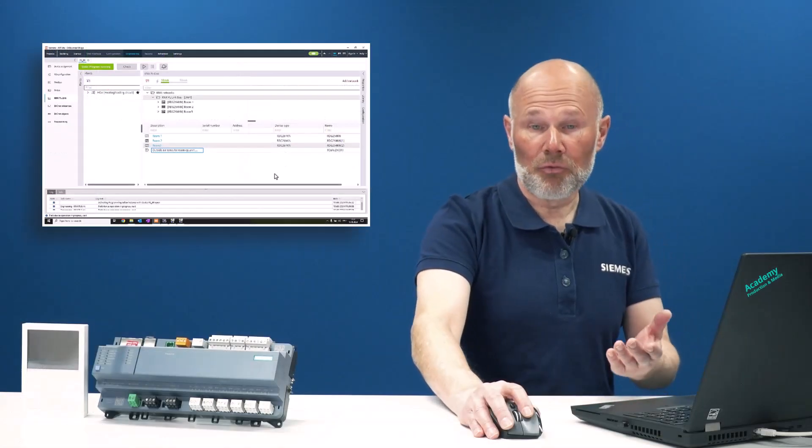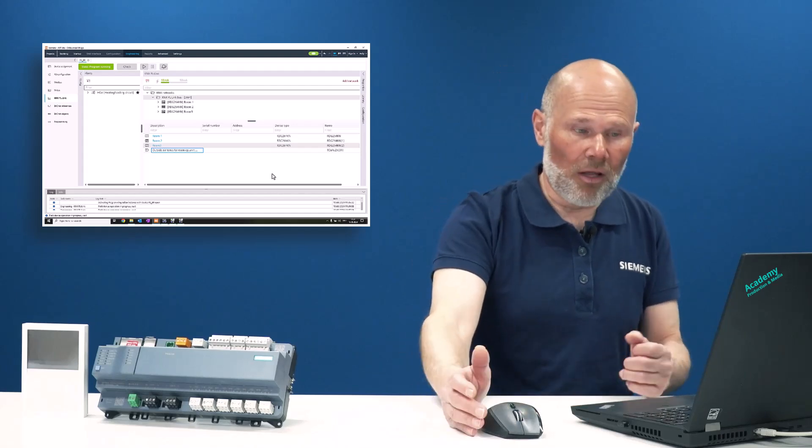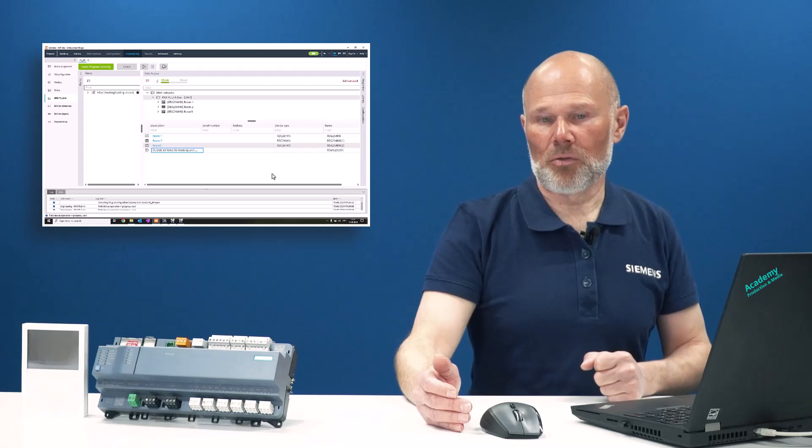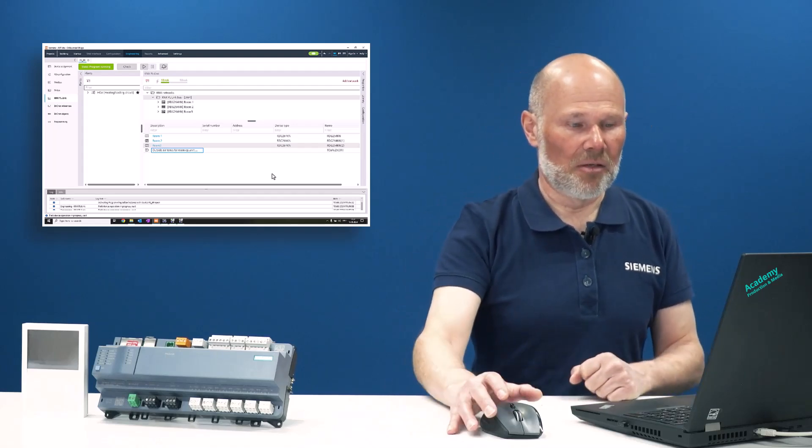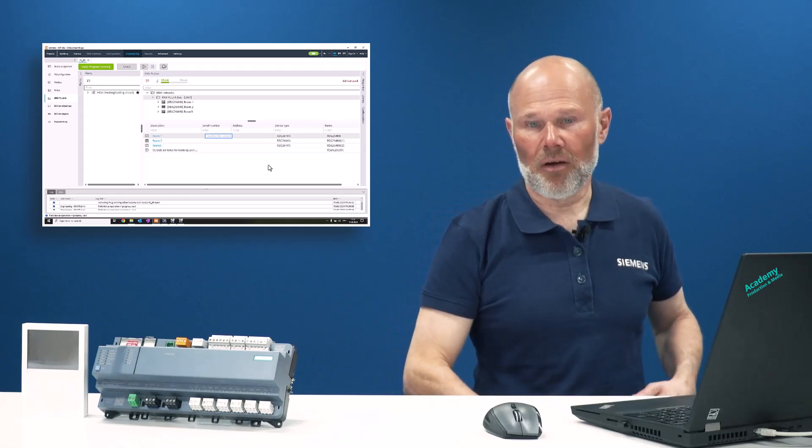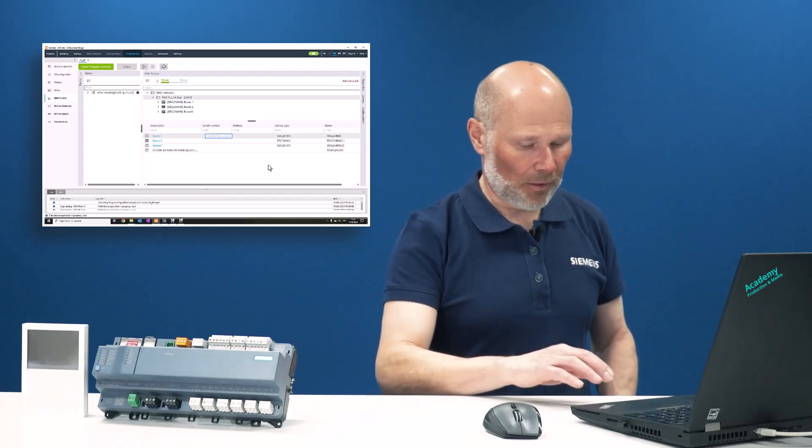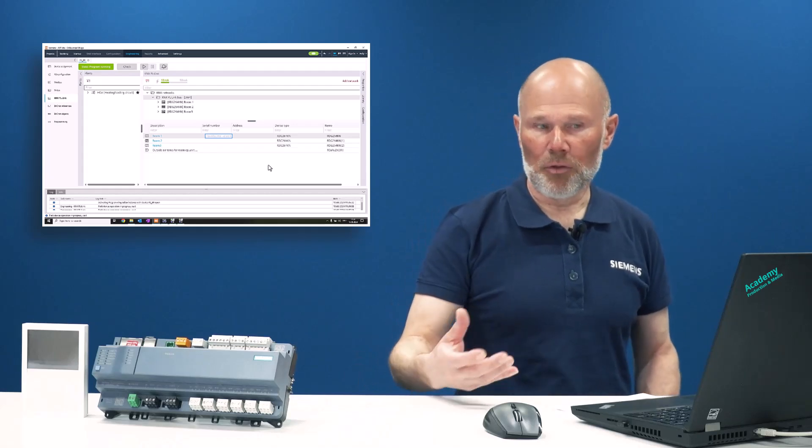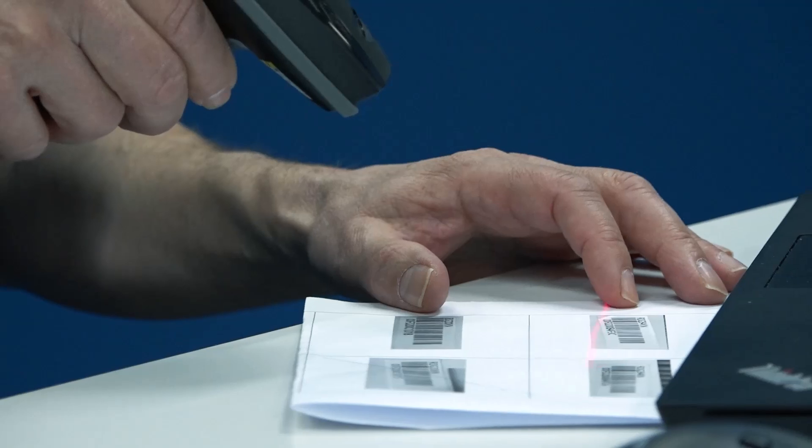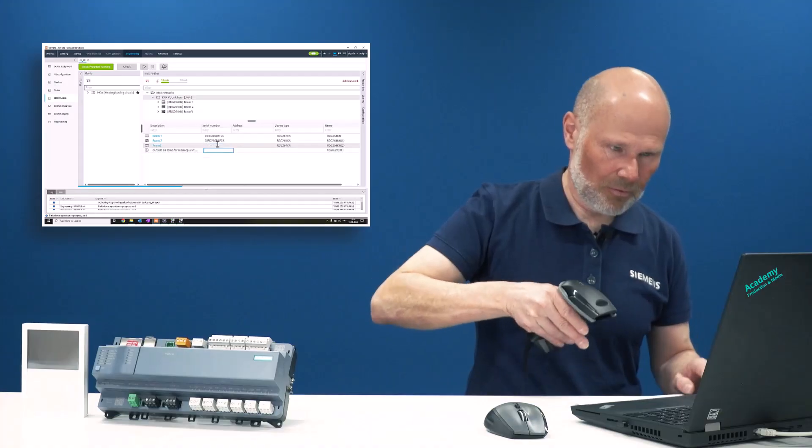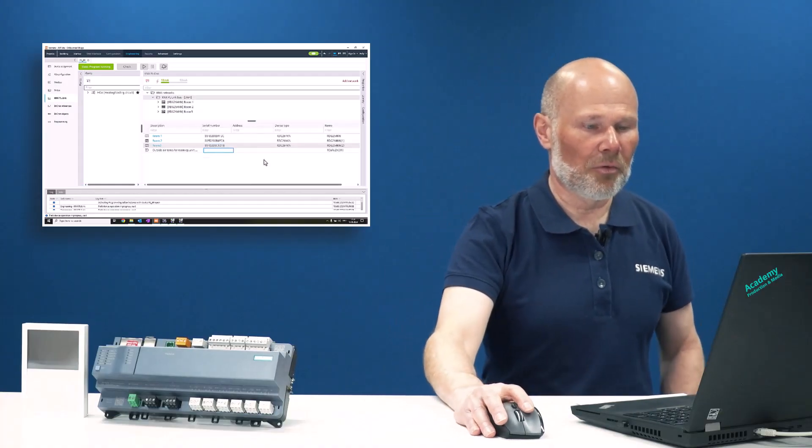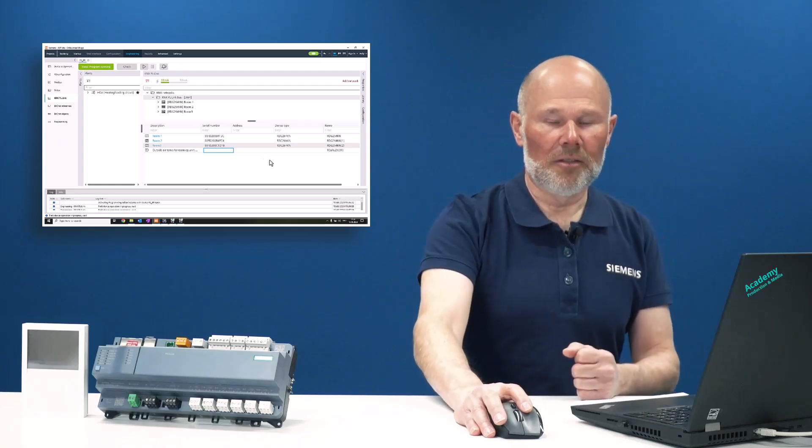The next step, step three, is the assignment. We can do it offline, which is the preferred way, or online using the service pins of the devices. Offline has advantages because we can use the serial number of the device. We have a nice feature where we can use a barcode reader. By reading the barcodes from the devices, which are on stickers in the package, you put the sticker on a floor plan so you know the location and simply scan with a scanner: first one, second one, and the third one. We've automatically read in the serial number, which is enough to auto-assign the device when you download.